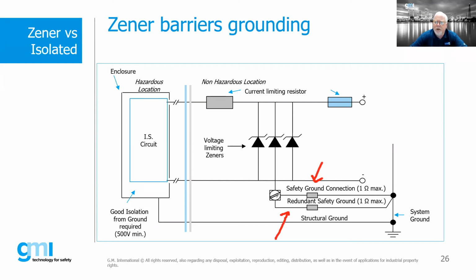So it is good engineering practice to have a redundant safety ground that is separate from our normal safety ground, so we can check the resistance of our safety ground periodically. That's very good engineering practice. It's not necessarily something that must be done, but it is commonly done, if you will.